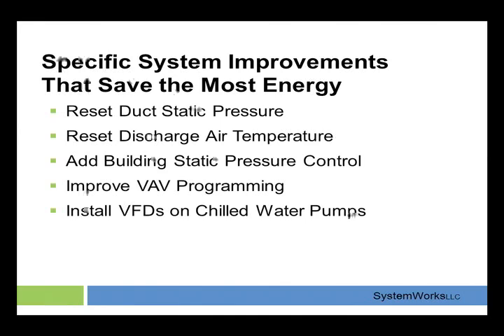Building static pressure control is something we did here, and this is when you walk in a building and the doors are either standing open because the building's too positive, or you can't get the door open. It's tight, and that's usually the case. Buildings are negative. They're pulling in cold air, hot air, and unconditioned air, and that causes a lot of problems. So getting the building pressure under control is critical. VAV programming is variable air volume boxes. Those are typically the controls in a classroom.